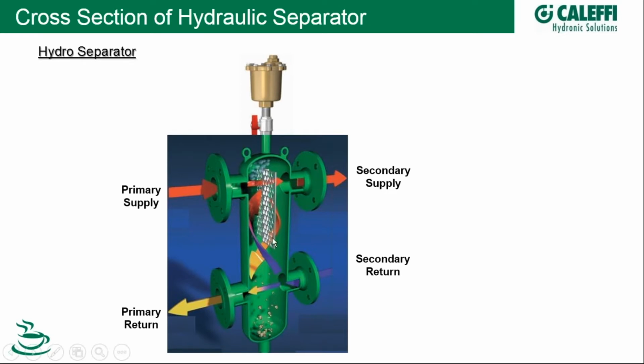So it's a flow straightener, and you can see two helical arrows here. It's kind of an artist's rendering. They would never happen like this in two different directions at one time. You're either going up or you're going down, or there isn't any flow. In the event that your primary flow rate and your secondary flow rate are equal, you wouldn't have any vertical travel of flow, okay? So they're designed to allow flow to be vertical, either in an upward fashion or downward fashion. And a baffle plate minimizes any turbulence.